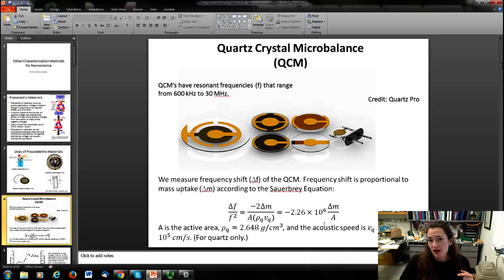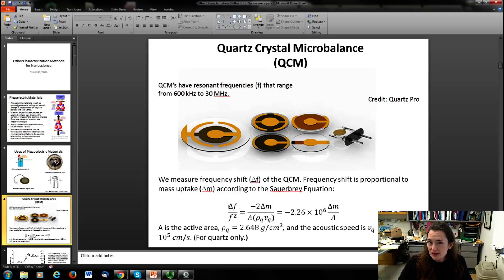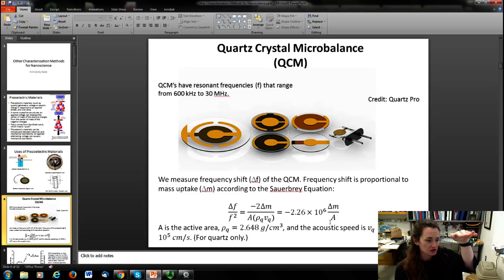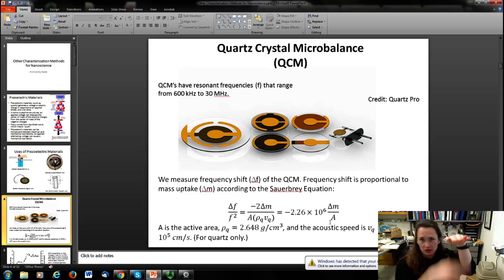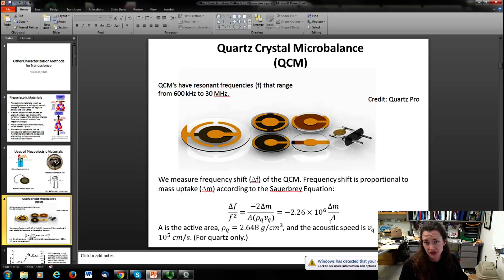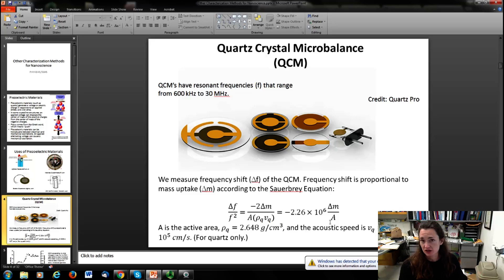With high resonant frequencies (600 kHz to 30 MHz), the frequency shifts are a reasonable size for very small mass uptake. For example, inside a vacuum chamber you can expose the resonator to a thin film — adsorbed from vapor or deposited by thermal evaporation — and the QCM measures the mass. This makes QCMs very useful as microscale weighing devices and for determining thin film thickness in nanotechnology and nanoscience.